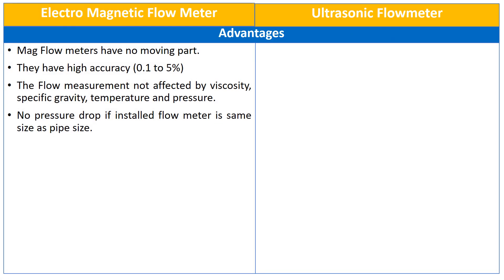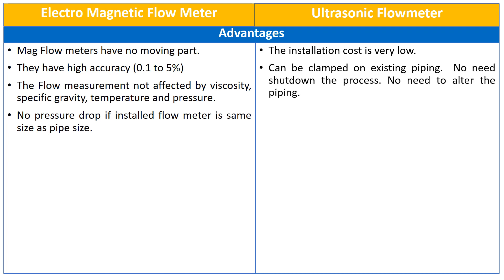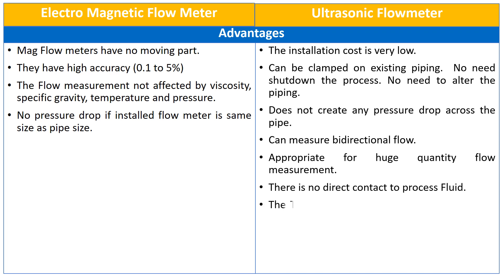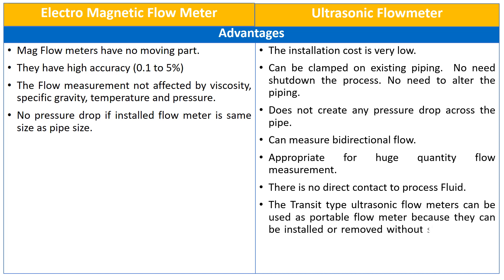Let us see some advantages of ultrasonic flow meters. The installation cost of these flow meters is very low. They can be clamped on existing piping with no need to shut down the process or alter the piping. They do not create any pressure drop across the pipe, and they can measure bidirectional flow. Ultrasonic flow meters are very appropriate for huge quantity flow measurement. There is no direct contact with the process fluid. The transit type ultrasonic flow meters can be used as portable flow meters because they can be installed or removed without shutting down the process.